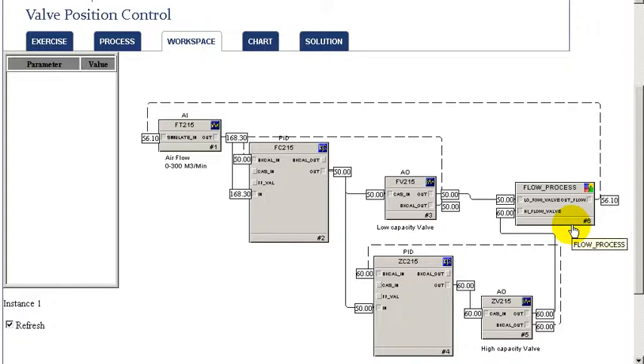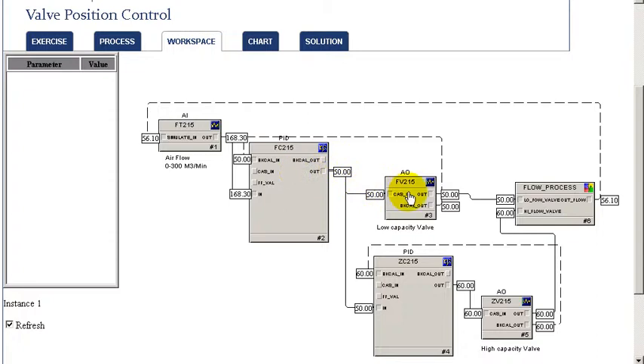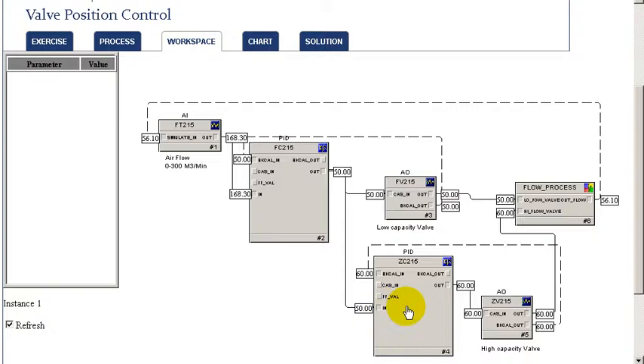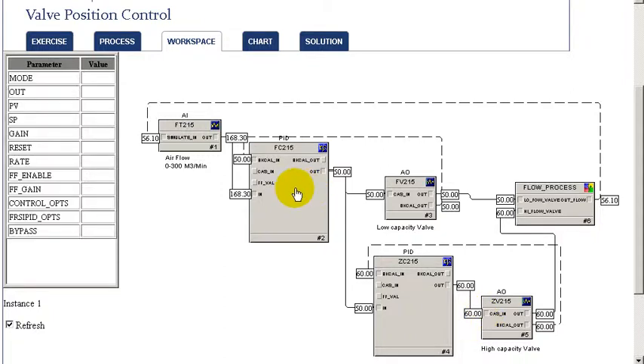In the simulation, we take into account both the small valve and the big valve in determining the flow. The flow is then controlled using a PID control that's adjusting the smaller valve. The output of that PID is then used as the input to our valve position controller, the integral-only controller that is then used to adjust the larger valve.